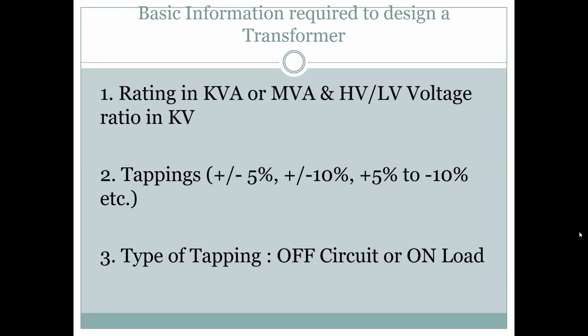Now, tappings. As I was telling, we do not get quality power by transmission, so there is always fluctuation. With every fluctuation, the transformer should not trip on over voltage or under voltage. The transformer should be allowed to function with those variations of voltage. Right now I am getting 33 kV, it goes down to 31.5 kV, it goes up to 36 kV. During peak season, summer and winter, a lot of things take place. The tapping windings are there. Suppose it is 132 by 33, the output should be 33. Whatever the 132 kV that comes to you, whether it is 135 or 131, it doesn't matter. With this tapping correction, you have to get 33 kV smooth.